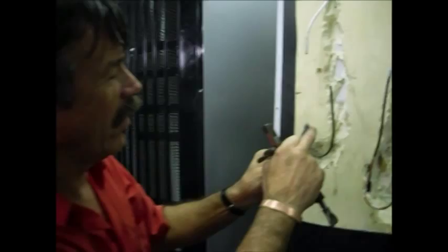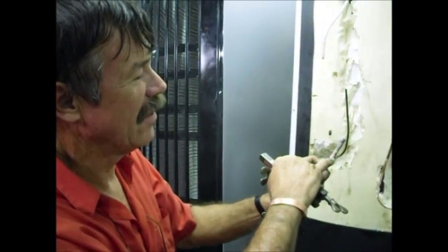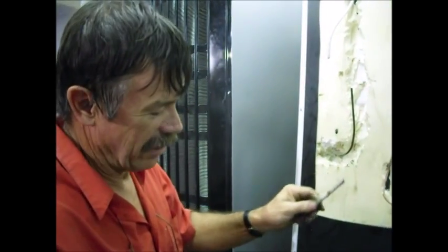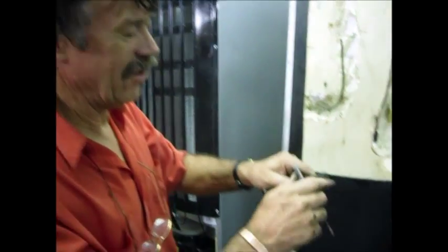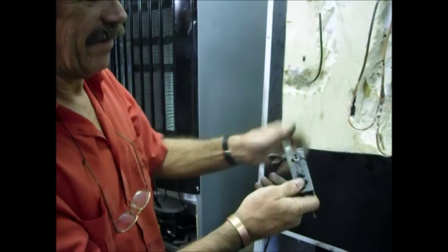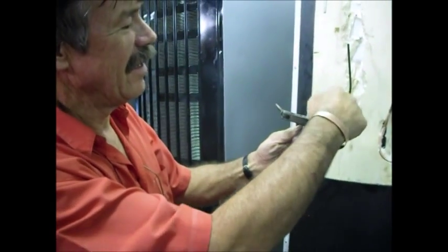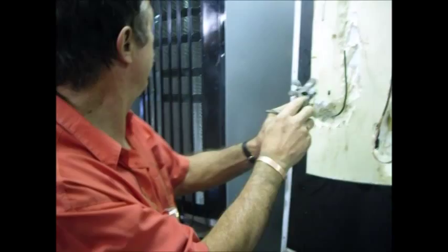The disadvantage of this when you weld it is a tremendous amount of heat will damage this joint. So to overcome that we clamp this into a flaring block like this and when you do the weld, the flaring block absorbs all the heat.